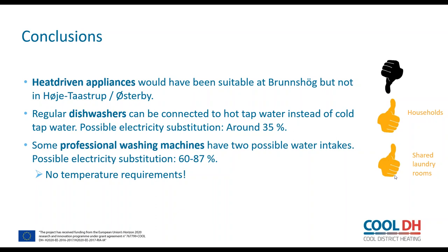And in Brunnshög, in Sweden, the supply temperature in the grid will be approximately 65 degrees Celsius, which means that the possible temperature in any secondary circuit will be around 55 to 60 degrees, and it would therefore comply with the temperature requirements given by ASCO. In Høje-Taastrup, on the other hand, the supply temperature in the grid will only be 55 degrees, and the secondary circuits will not be able to keep a temperature of 55 degrees or higher without adding electricity. And if you add electricity, then the benefits of the heat-driven appliances are counteracted.